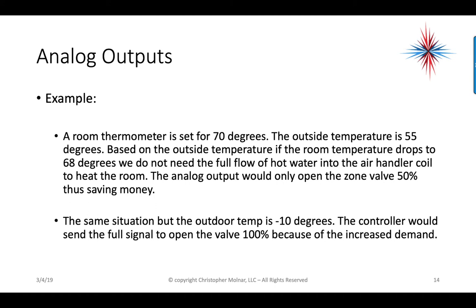An example: a room thermometer is set for 70 degrees and the outside temperature is 55 degrees. If the room temperature drops to 68 degrees, we do not need the full flow of hot water in the air handler coil to heat the room. The analog output would only open the zone valve 50%, thus saving money. In the same situation, if the outdoor temperature is negative 10 degrees, the controller would send the full signal to open the valve 100% because of the increased demand. If the outdoor air temperature is warmer, the building is losing less heat and we only need 50% of our full potential.